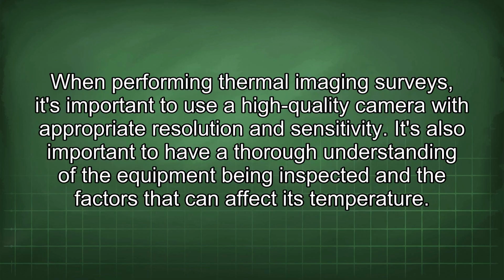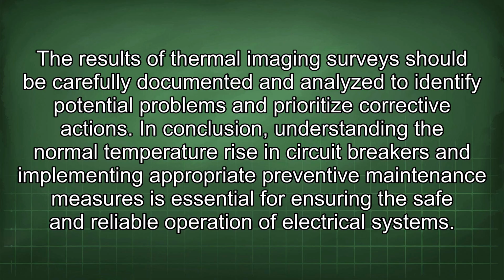When performing thermal imaging surveys, it's important to use a high-quality camera with appropriate resolution and sensitivity. It's also important to have a thorough understanding of the equipment being inspected and the factors that can affect its temperature. The results of thermal imaging surveys should be carefully documented and analyzed to identify potential problems and prioritize corrective actions.